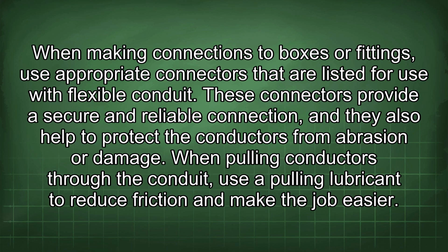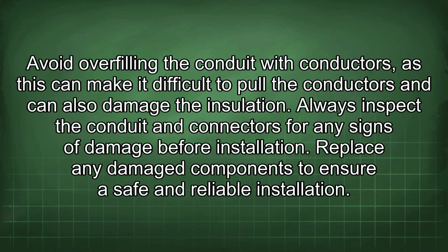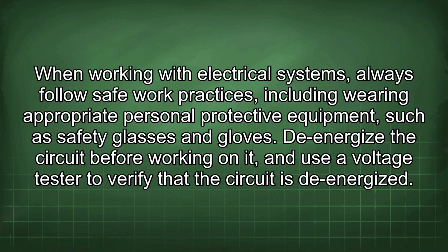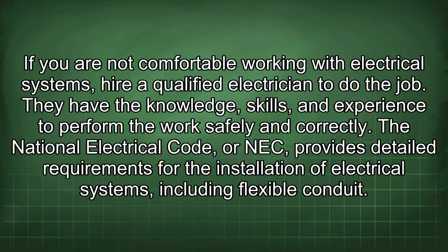When pulling conductors through the conduit, use a pulling lubricant to reduce friction and make the job easier. Avoid overfilling the conduit with conductors, as this can make it difficult to pull the conductors and can also damage the insulation. Always inspect the conduit and connectors for any signs of damage before installation. Replace any damaged components to ensure a safe and reliable installation. When working with electrical systems, always follow safe work practices, including wearing appropriate personal protective equipment such as safety glasses and gloves. De-energize the circuit before working on it, and use a voltage tester to verify that the circuit is de-energized. If you are not comfortable working with electrical systems, hire a qualified electrician to do the job. They have the knowledge, skills, and experience to perform the work safely and correctly.